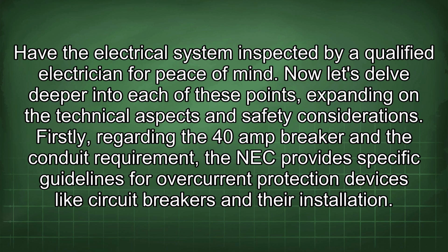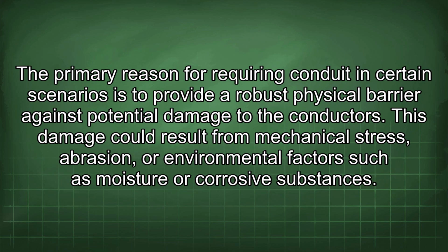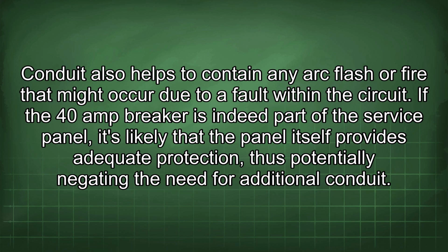Now let's delve deeper into each of these points, expanding on the technical aspects and safety considerations. Firstly, regarding the 40 amp breaker and the conduit requirement, the NEC provides specific guidelines for overcurrent protection devices like circuit breakers and their installation. The primary reason for requiring conduit in certain scenarios is to provide a robust physical barrier against potential damage to the conductors. This damage could result from mechanical stress, abrasion, or environmental factors such as moisture or corrosive substances. Conduit also helps to contain any arc flash or fire that might occur due to a fault within the circuit.